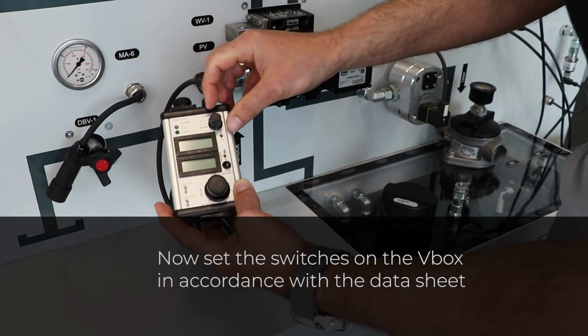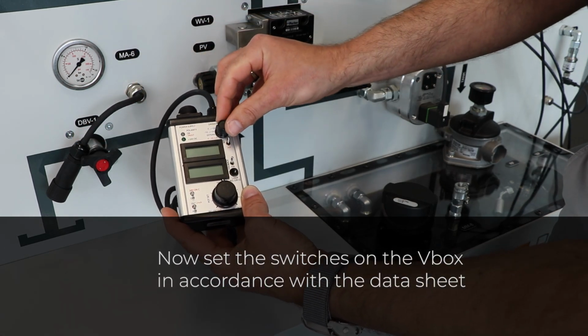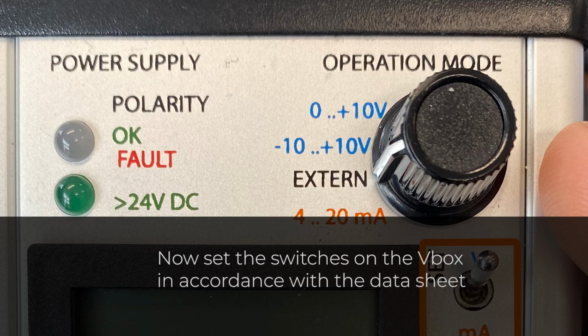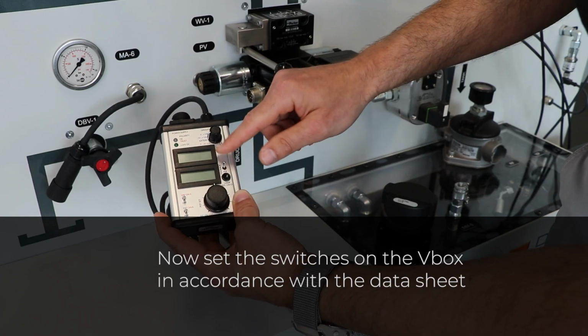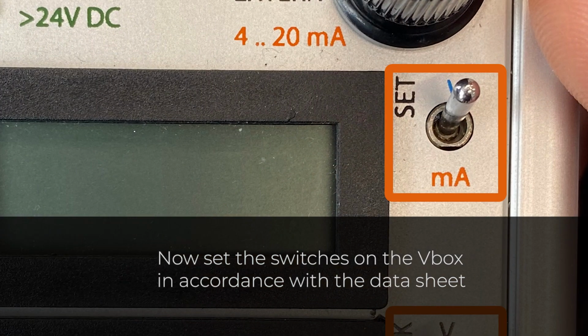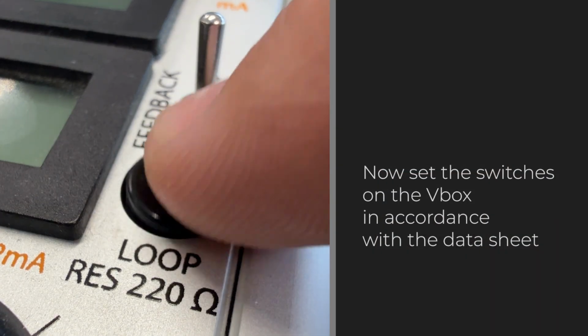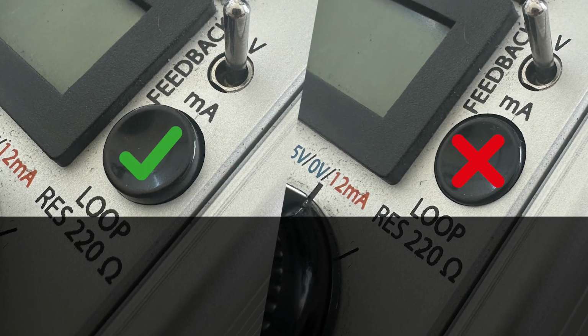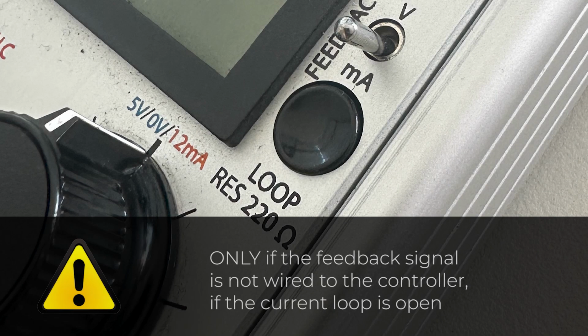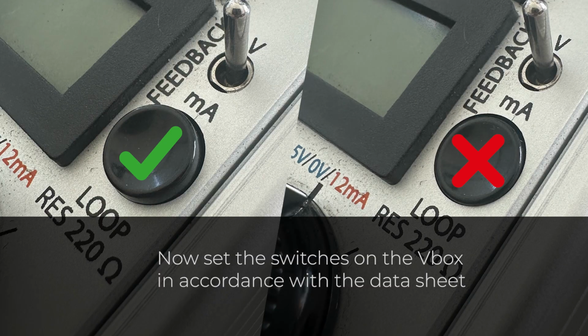In our example, we set the Vbox as follows: Operation mode, extern. With this setting, the setpoint signals from the control system are initially displayed on the Vbox. We set the display for the setpoint signal to volt. We set the display for the feedback signal to volt. If volt has been selected on the feedback signal display, the loop push button must generally not be pressed. The loop push button is pressed only if the feedback signal is set to milliamps and is not connected to the control system, meaning that the current loop is open. For more detailed information, please refer to our operating manual.